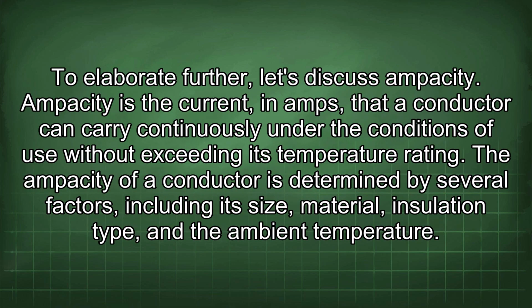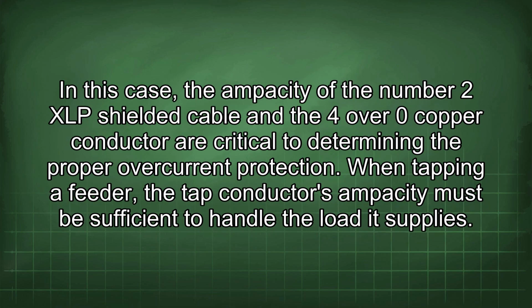To elaborate further, let's discuss ampacity. Ampacity is the current, in amps, that a conductor can carry continuously under the conditions of use without exceeding its temperature rating. The ampacity of a conductor is determined by several factors, including its size, material, insulation type, and the ambient temperature. In this case, the ampacity of the number 2 XLP shielded cable and the 4/0 copper conductor are critical to determining the proper overcurrent protection.